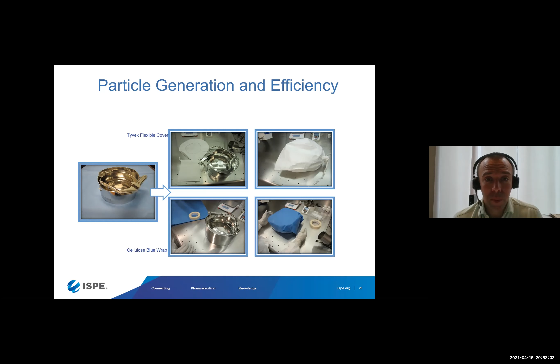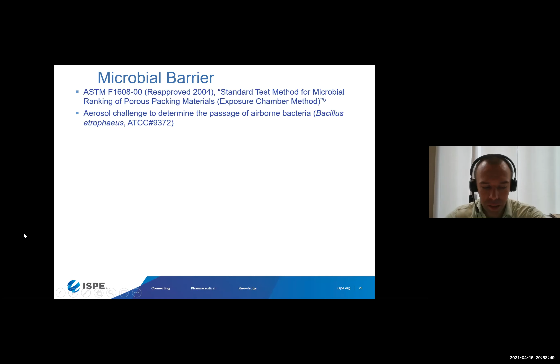And I also mentioned earlier that there was a difference in microbial barrier properties. So here we did tests using a standardized ASTM method. This is for microbial ranking of porous packing materials. This ASTM challenge is using airborne bacteria, Bacillus atrophaeus spores, in an aerosol form to measure the passage of bacteria through the material. It's really a filtration efficiency test. So we tested the rigid polyolefin, a flexible polyolefin, the blue cellulose wrap, and then the rigid kraft paper wrap.